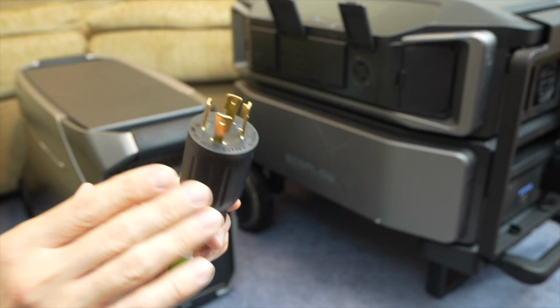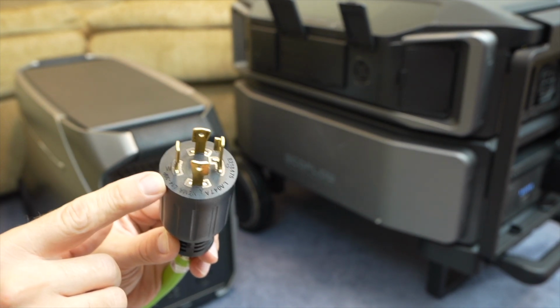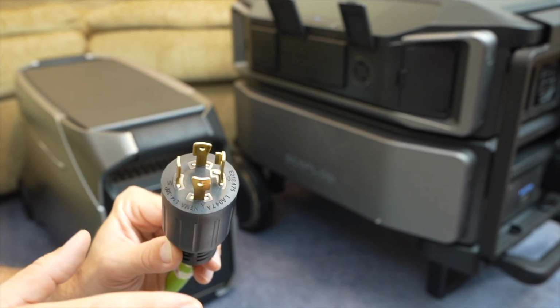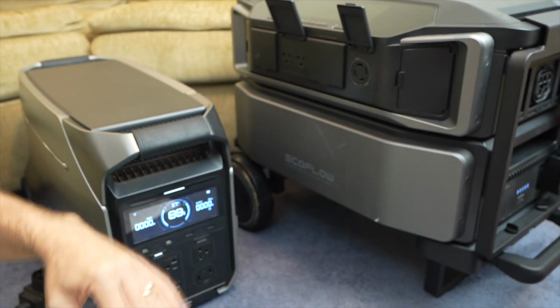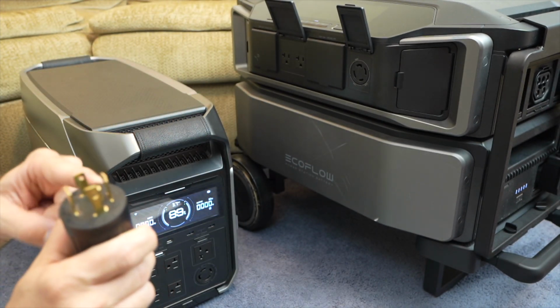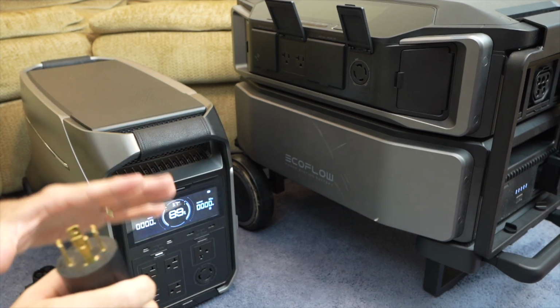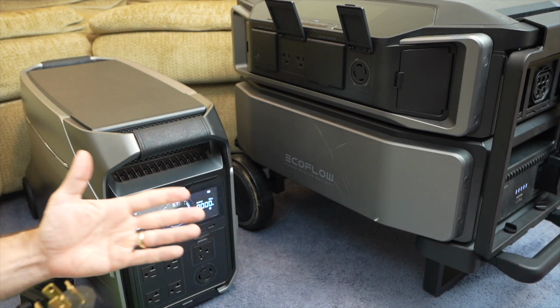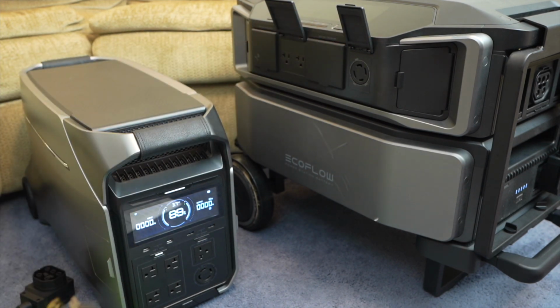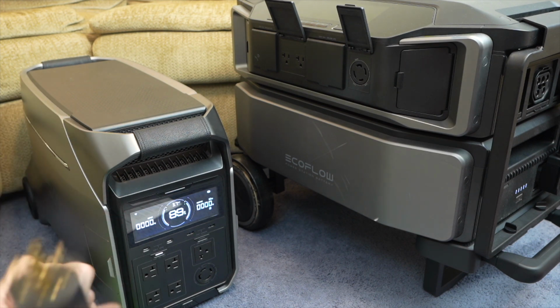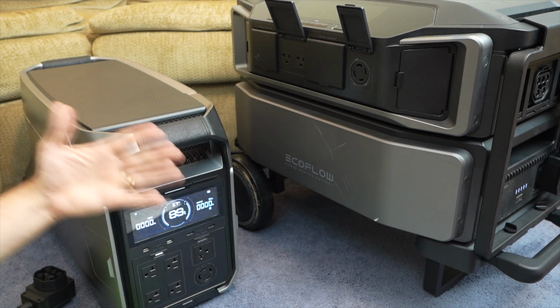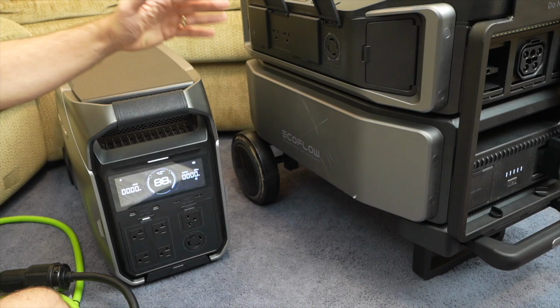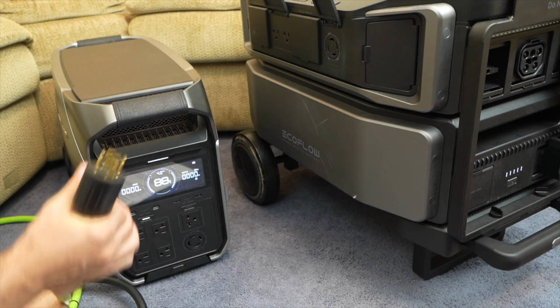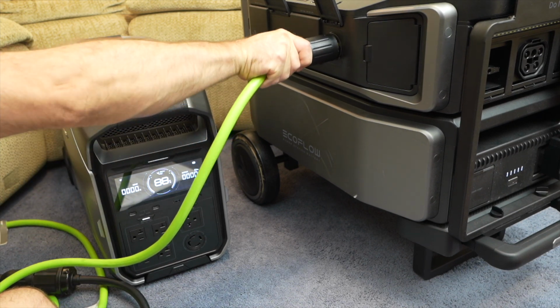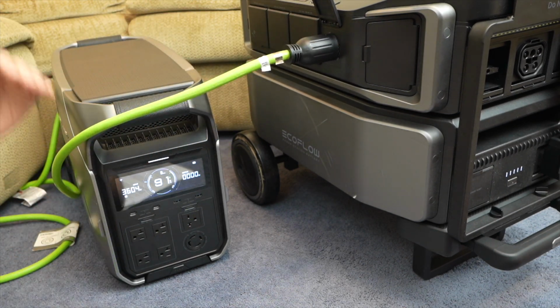To understand those maximums in a little bit more detail, here's a 240 volt plug. Two of these connections are the 120 volt connections. So on the Delta Pro 3, only one of these can handle about 16.6 amps, and the other one can handle 16.6 amps. And then on the Delta Pro Ultra, each one of these can be 30 amps. So what that means is that if you have this connected and one of these 120 volt legs goes over that limit, it's going to put the inverter into overload. So that difference in AC output can make quite a bit of difference. If you're trying to back up your whole house, you have to add up all the loads to make sure that the AC inverters can handle it.